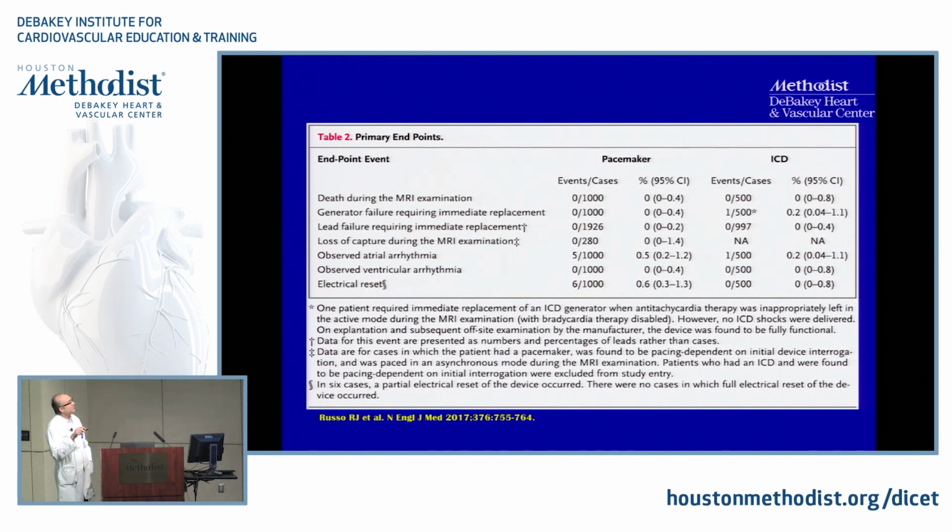There were no cases of lead failure requiring immediate lead replacement, and no cases of loss of capture during the MRI examination. There were some observed atrial arrhythmias, and again, that's just a function of the underlying rhythm abnormalities that these patients can have. And there were a few cases of electrical resets, which means that the device reset.